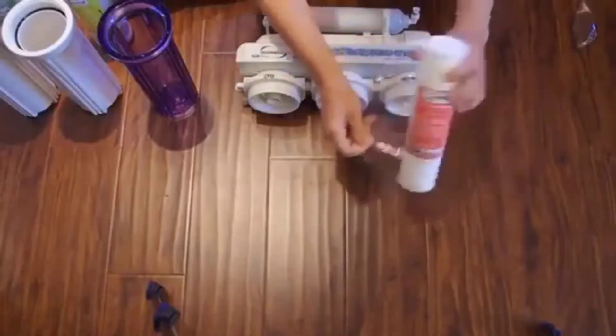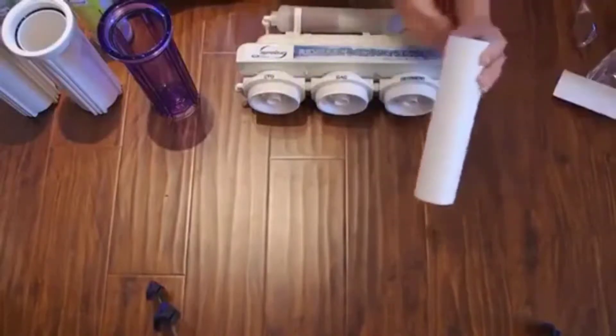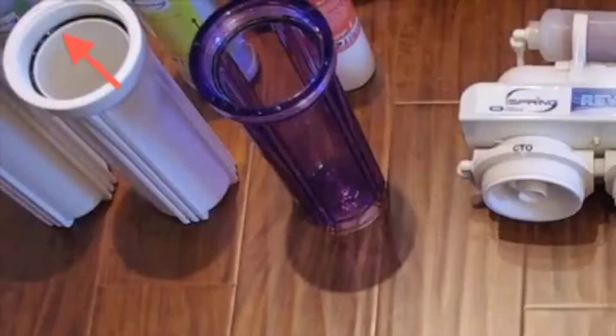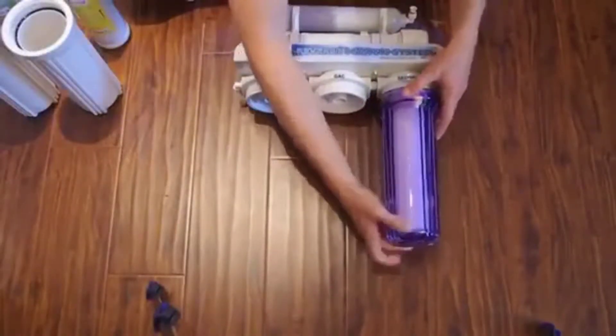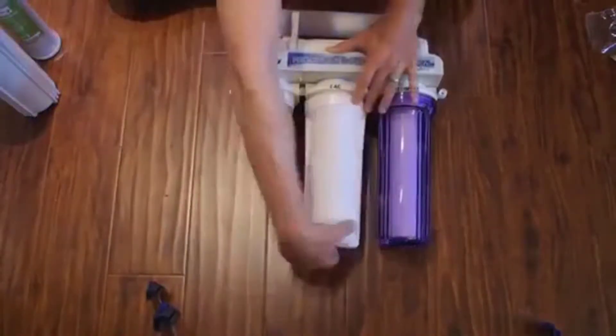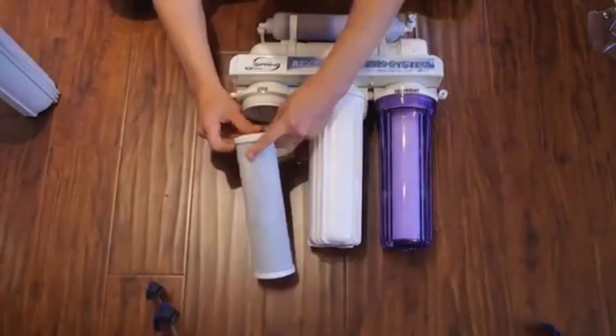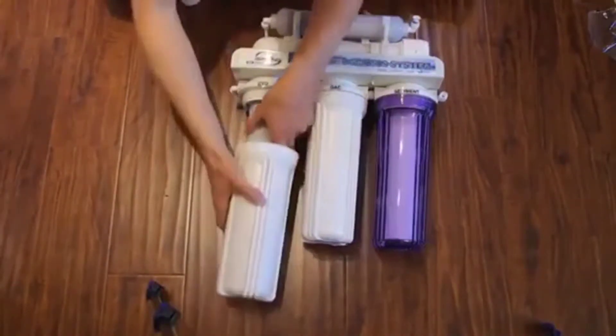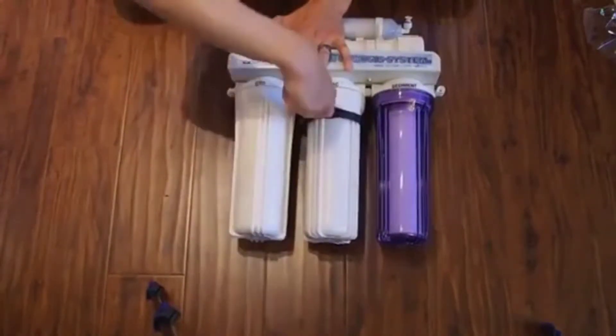Remove the protective wrap from each filter when installed. Make sure the O-ring is seated in the top of the housing. Install the filter in the housing and then hand-tighten the housing onto the filtration system. Installing filter elements vertically will help keep them aligned when you thread on the housing. Repeat the process for the two remaining filter elements, making sure to match the correct orientation. Tighten filter housings using the speed wrench.